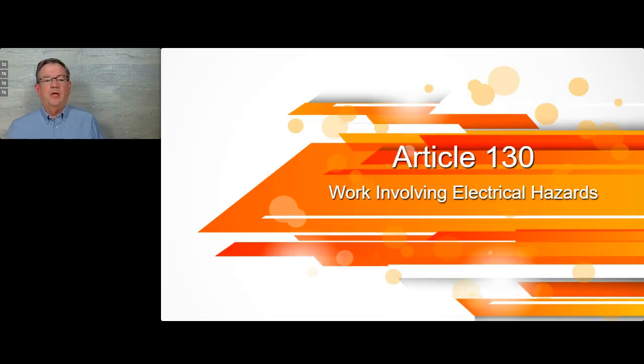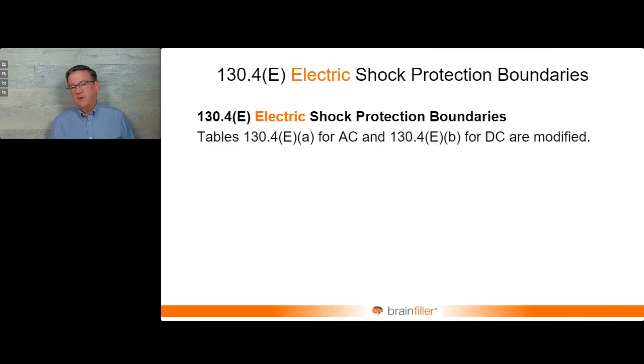Article 130, this is where a lot of focus happens, focusing on what you do if we're going to be working around electrical hazards. And you might think, well, we de-energize everything. We always make it electrically safe. That's fantastic. That is the goal. But the process of creating an electrically safe work condition in itself potentially exposes you to hazards. The shock hazard until you verify there's no voltage. The arc flash hazard until you verify, again, there is no voltage or no hazard there.